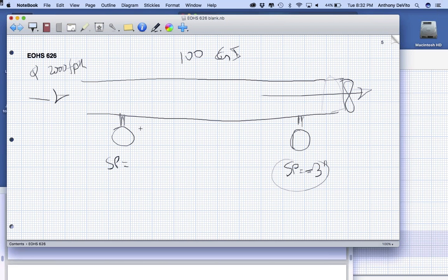The static pressure here is lower, right? Static, or in a sense, higher. It might be negative 2 inches. Because what happened? You have resistance to the airflow in that ductwork. So this, in a sense, is energy. It's potential energy. The only reason the air is moving is because you've got a negative pressure relative to outside the duct of 3 inches.